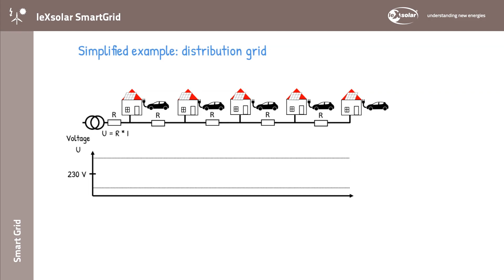In the first summer scenario, we consider a sunny day. All PV systems feed in at full load since the household storage is already full and consumption is low since no one is at home. Approximately each household feeds in a current of 10 kilowatt divided by 230 volts, rounded down to about 40 amps. The total current in the foremost section is thus 5 times 40 equals 200 amps.